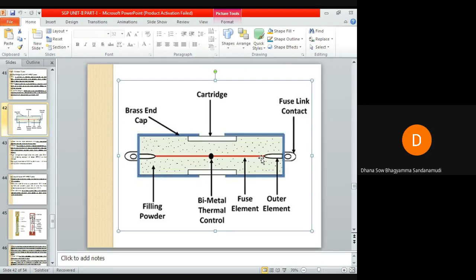In some designs there will be two fuse elements in parallel. You can see only one, but there will be two fuse elements, one of low resistance and the other of high resistance. The low resistance fusing element is silver wire and the high resistance fusing element is tungsten wire. So this cartridge type HRC fuse can have two fusing elements.